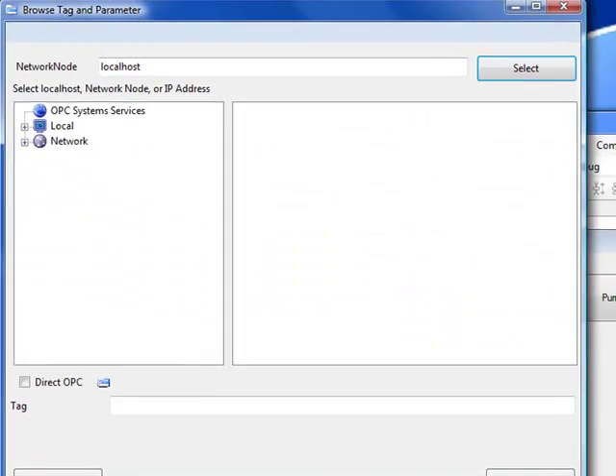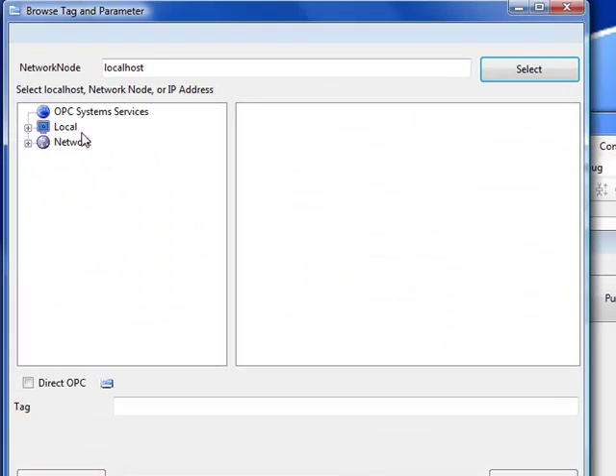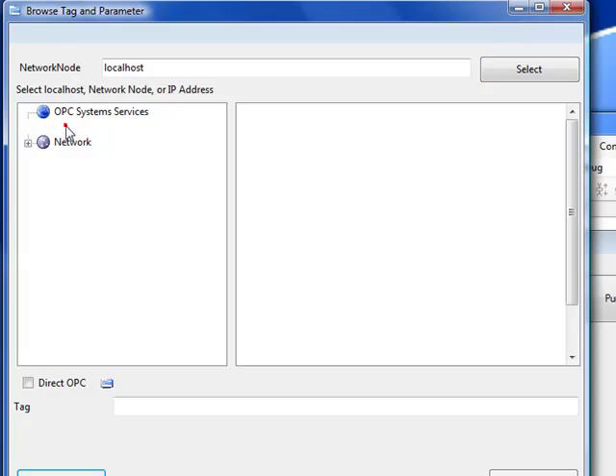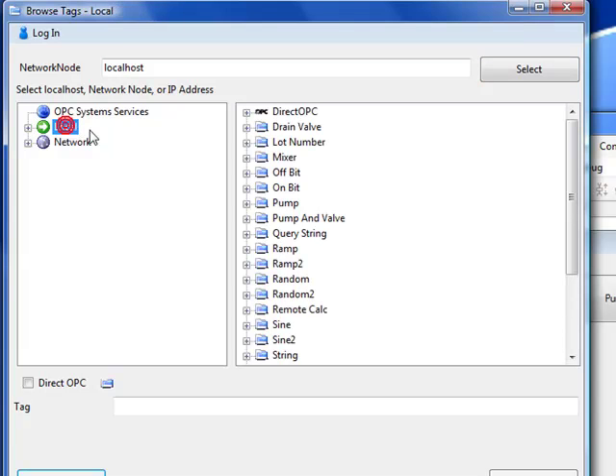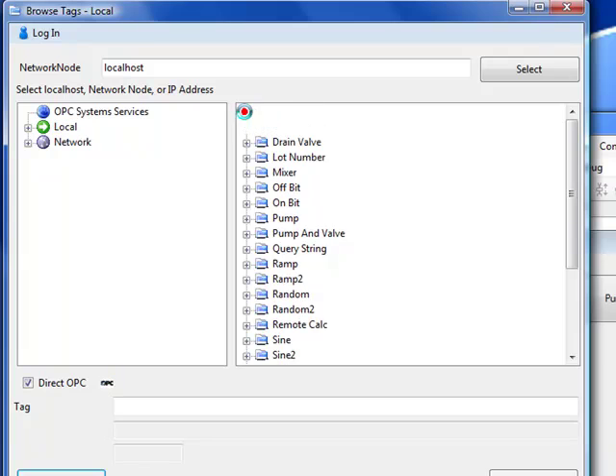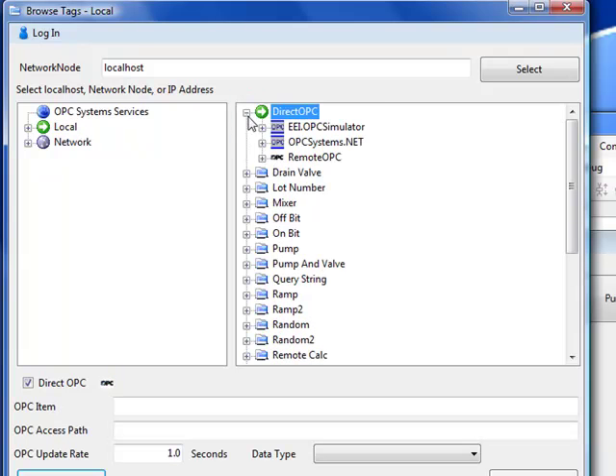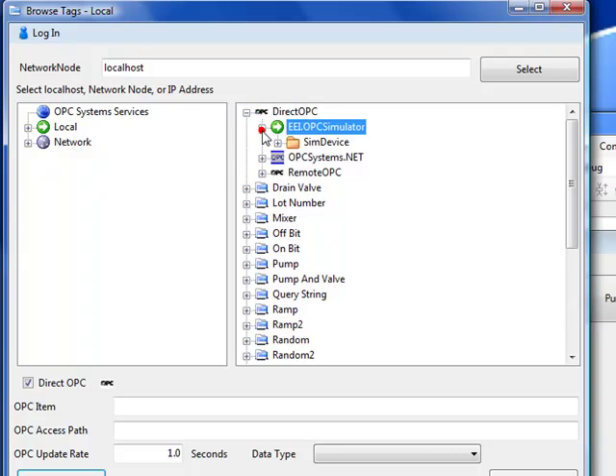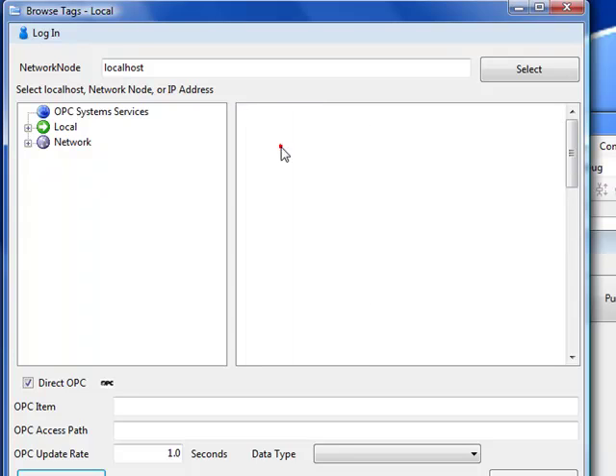We are going to go down to the text called text OPC systems underscore tag. We will browse for a particular tag on the local system. This time we're going to connect directly to an OPC server that we want to write a value to. To do that, we'll click on the plus sign to the left of direct OPC. This is a different data source type.